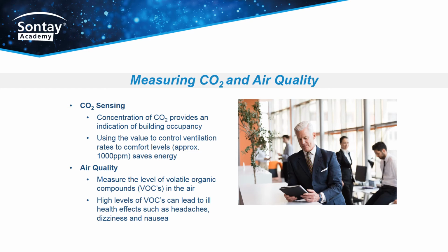Ventilation is provided to maintain good air quality, but a distinction should be made between the requirement to sense carbon dioxide and the requirement to sense general air quality. Carbon dioxide measurements are intended to give an indication of the occupancy level of a building, whereas air quality sensors sense a combination of airborne pollutants, including carbon dioxide. The correct sensor must be used for the required application, and when implementing demand-controlled ventilation, good quality carbon dioxide sensors are required rather than air quality sensors. More details on these applications are given in the following slides.